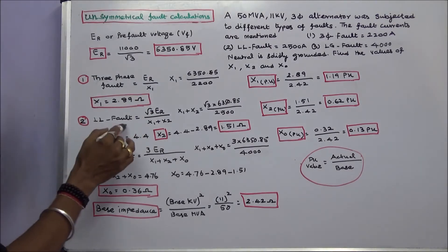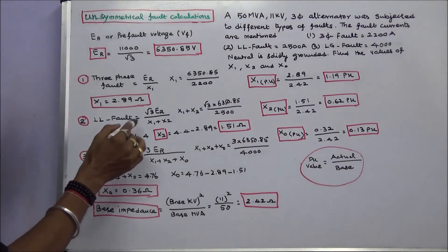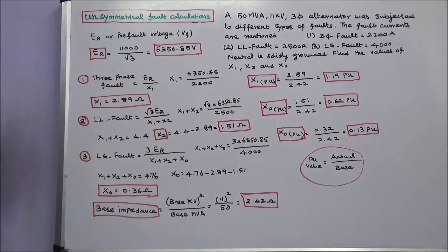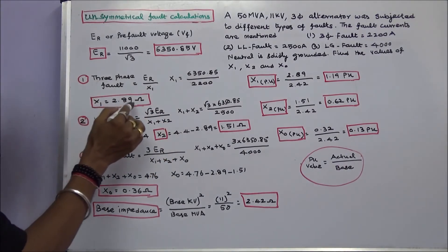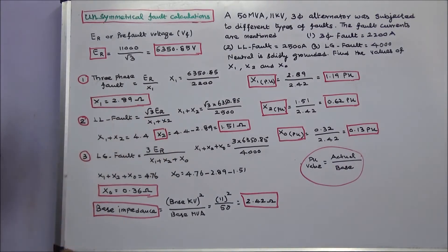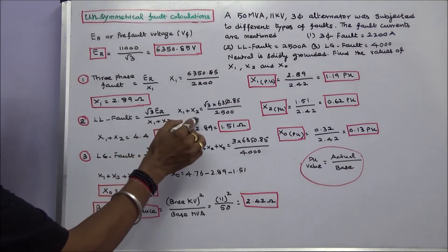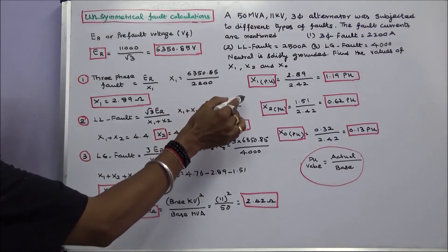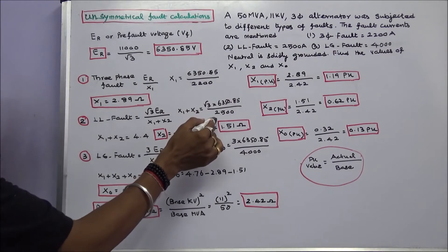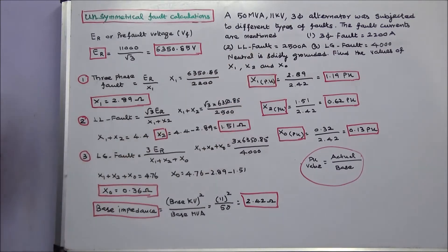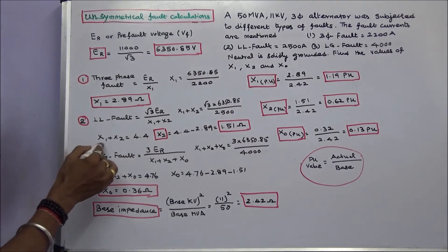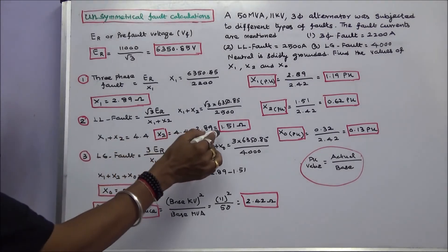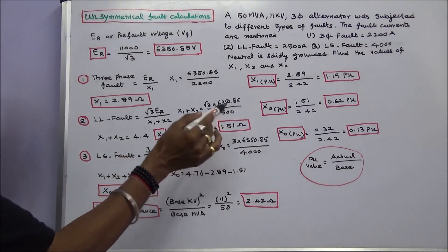For a line-to-line fault, the formula is root 3 multiplied by ER divided by (X1 plus X2). We know X1 is equal to 2.89 ohms. Therefore X1 plus X2 equals root 3 into 6350.85 divided by 2500, giving X1 plus X2 equal to 4.4 ohms. So X2 is equal to 1.51 ohms.